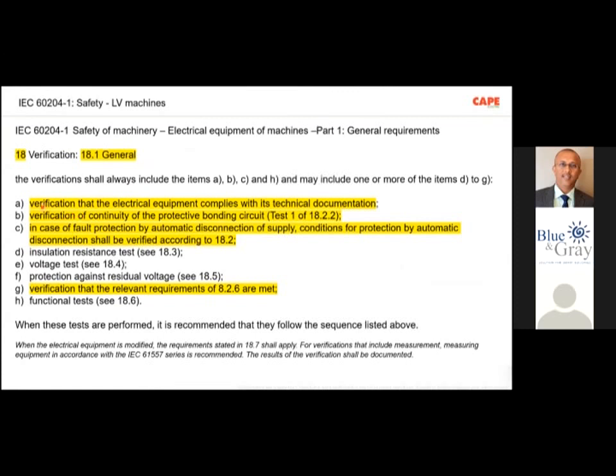Now, in all product standards, the first verification is that the electrical equipment complies with its technical documentation. That means you are getting a catalog, a brochure, manuals, and test reports, and first you find out whether these are up to the most modern standards, or up to the standards claimed by the manufacturer. That has to be verified first. That means the person doing this job must be aware of the standard, and should understand what kind of testing is required for each and every equipment, and should do it properly.